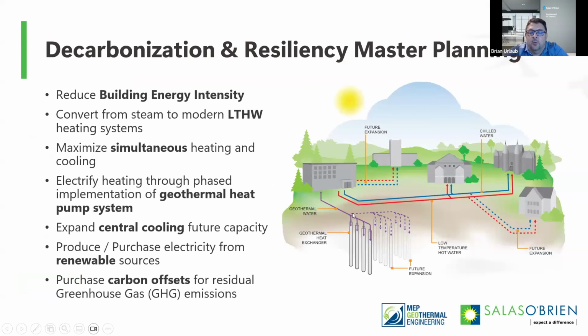With a closed loop system, there are two pipes that go down the hole. There's a supply pipe, the water goes down, exchanges energy, comes back up, and then goes back into the building. There are multiple bores, generally around 20 feet apart, and they can be anywhere from 300 feet to 1,000 feet deep, roughly. But they're not actually moving any water underground, just thermal exchange. For every roughly 200 feet of bore you get 12,000 BTUs, or 1 ton of capacity. So if you were going to do 500 tons, you need a lot of holes spaced 20 feet apart to meet that capacity, because the exchange rate is so slow with the earth and the plastic pipe that it takes a lot of ground mass and a lot of holes in the ground to exchange that much energy.